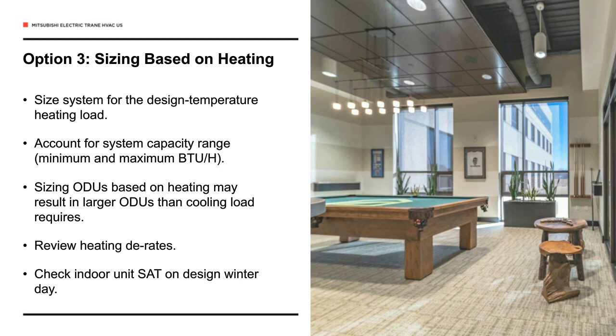The other thing we want to make sure to do in heating design is to look at the supply air temperature on your design winter day. That was a complaint with older heat pump technology, is that the units didn't make very warm air. Maybe it was able to keep up with the thermostat, but the discharge air was 78 degrees, and people just felt cold. Well, now with VRF technology, it's quite common on your design day to have discharge temperatures in the mid-90s and higher. I personally like to see a supply air temperature on my worst case winter day of something close to 90 degrees. Depending on the type of space it is, some spaces would be more sensitive to that than others. You might be able to get away with a little bit less. But you want to just make sure you're looking at your supply air temperatures, and that's shown as an output on the manufacturer's selection software. You can look at supply air temperature at given conditions.